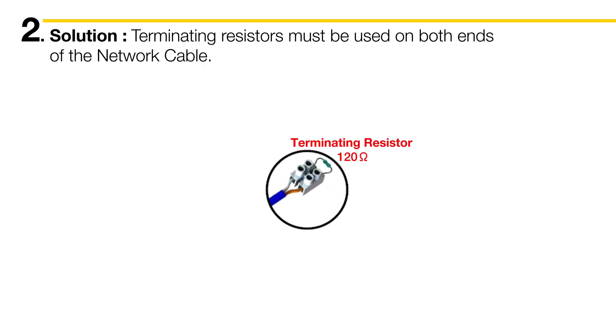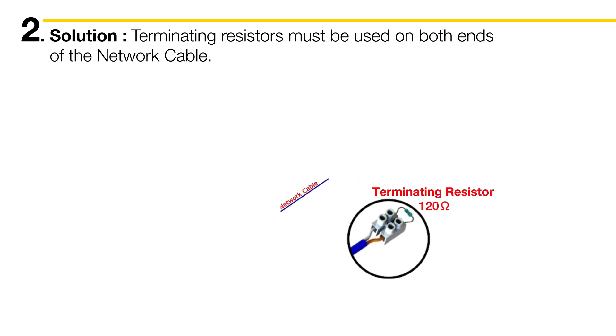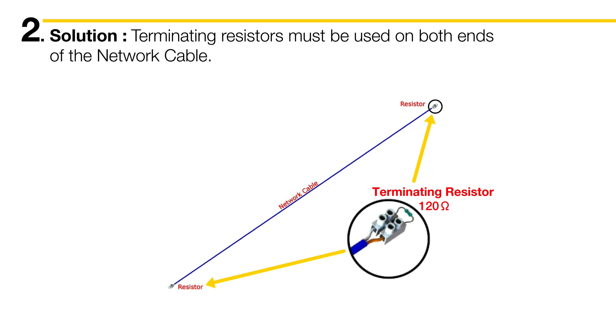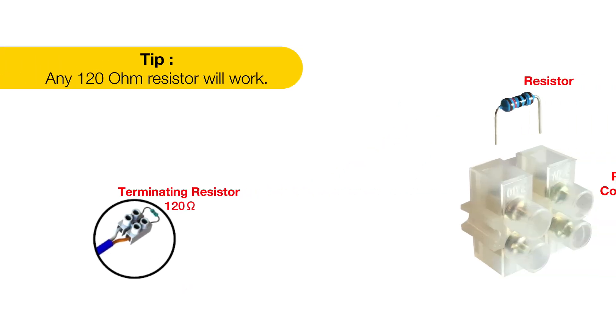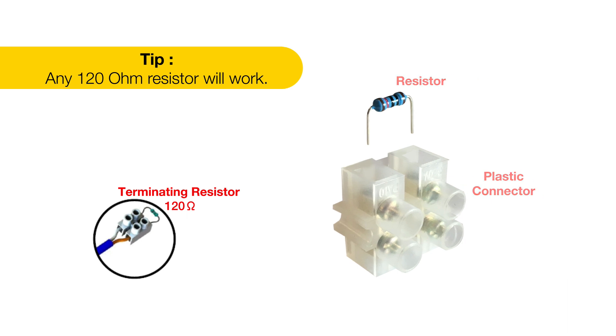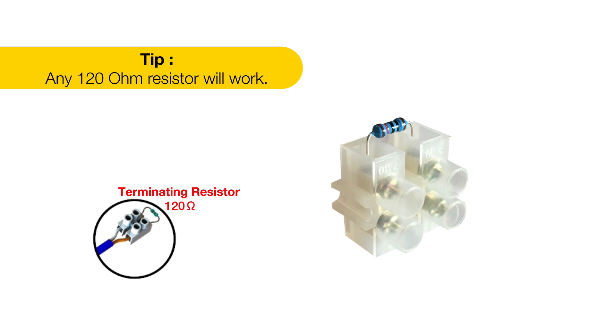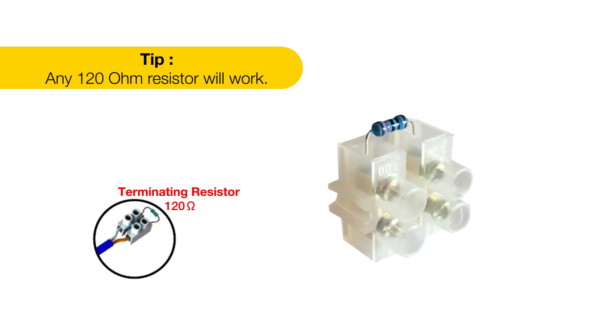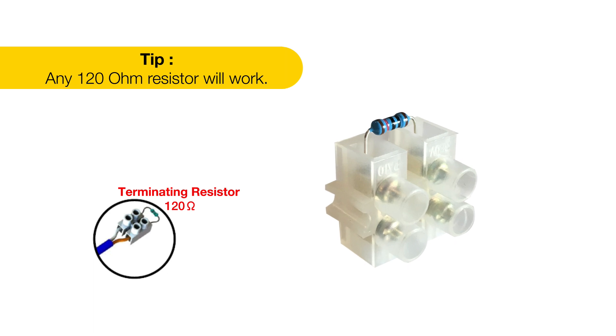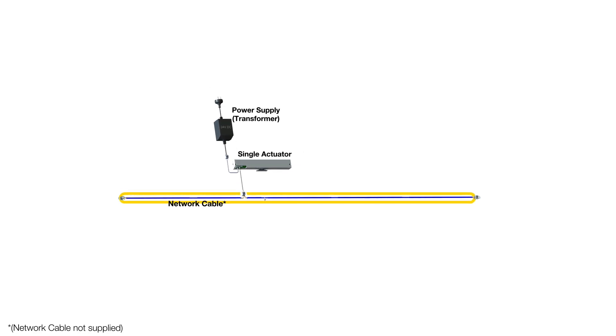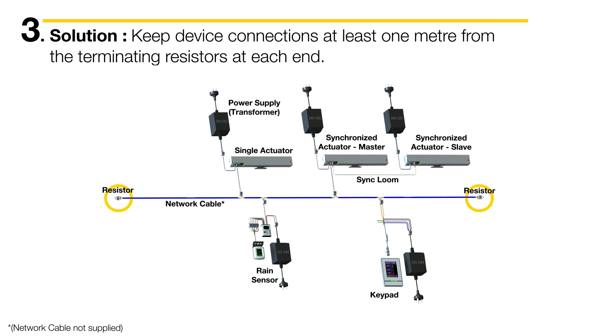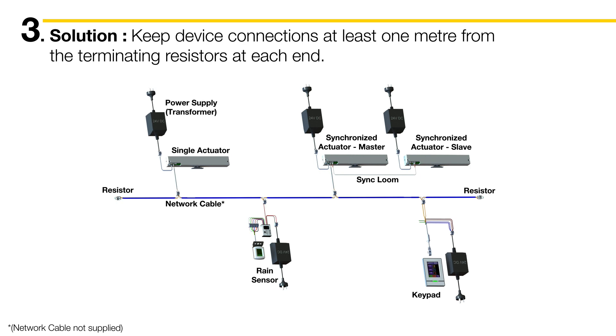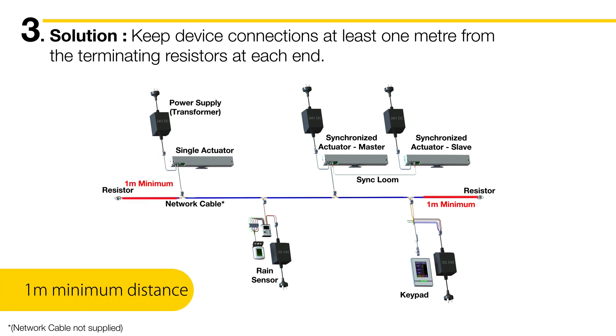The second issue you might find with the network cable is incorrect application of the terminating resistors. The Elevation system uses bus communication, so you must have a terminating resistor installed on each end of the network cable. These are critical for completing the data circuit and enabling communication to flow through the network. If you've lost the resistors supplied with the system, any 120 ohm resistor from an electronics store will do the trick. Test the resistors are 120 ohms before proceeding with the install — anything else will not work. All devices on the Elevation system tee off of the network cable between the two terminating resistors, and these connections can be anywhere along the network cable except within one metre from the terminating resistors at each end.